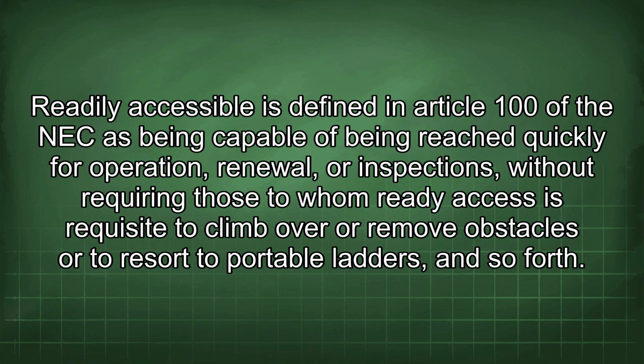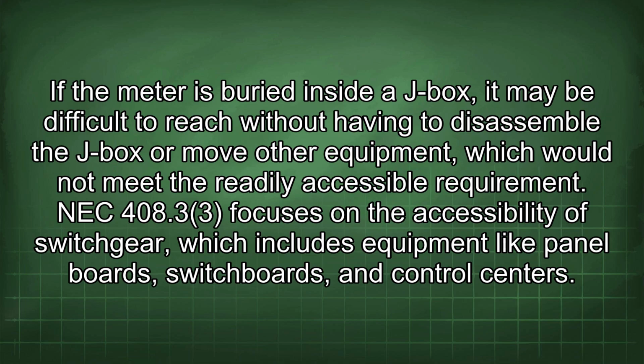Readily accessible is defined in Article 100 of the NEC as being capable of being reached quickly for operation, renewal, or inspections, without requiring those to whom ready access is requisite to climb over or remove obstacles or to resort to portable ladders, and so forth. If the meter is buried inside a J-box, it may be difficult to reach without having to disassemble the J-box or move other equipment, which would not meet the readily accessible requirement.